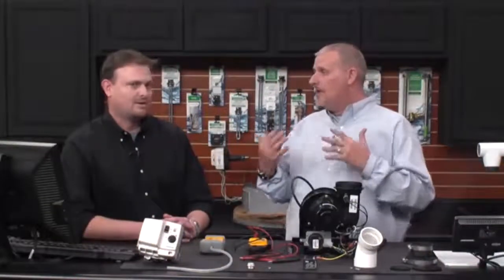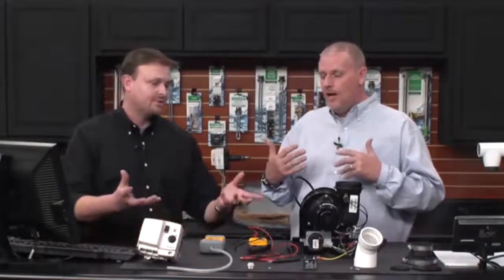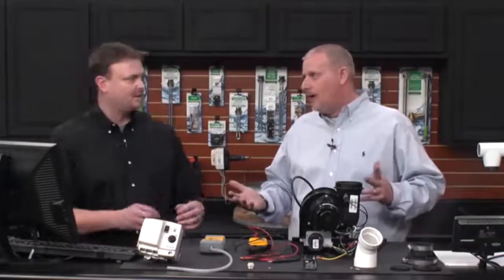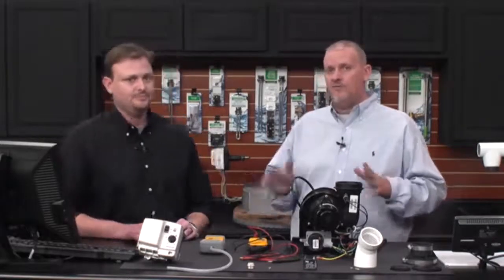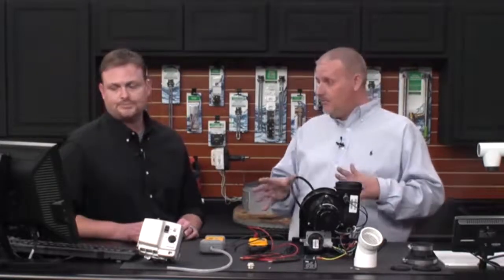There are certain circumstances where you may get some erratic flame or something may be pulling it away from the flame sense rod. Or gas pressure. But I would not start there. Not all that common. It's almost always a dirty flame sense rod. Clean the flame sense rod.